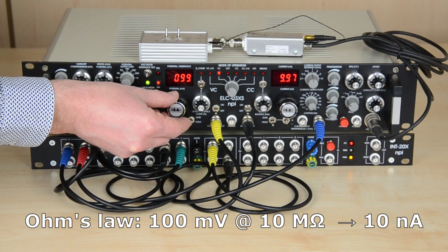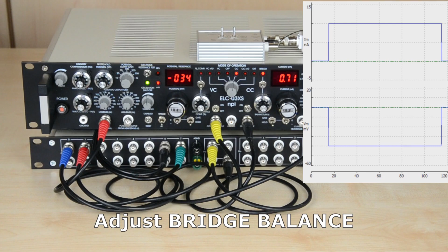The series resistance compensation in voltage clamp is based on the bridge balance. Therefore, we have to start in current clamp and do the bridge compensation there before switching to voltage clamp. We do this by applying a test pulse as described in the current clamp video.